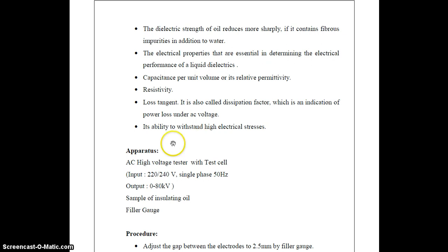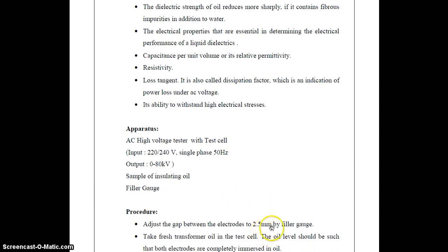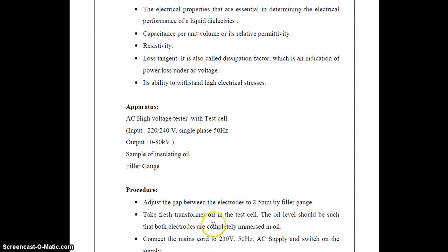Then the apparatus required for dielectric strength of liquid material is an AC high voltage tester with test cell. Input voltage is 220 volt to 240 volt, single phase, 50 hertz. Output is 80 kilovolt. A sample of insulating oil and a filler gauge are needed. Procedure: adjust the gap between the electrodes to 2.5 mm using the filler gauge. Take fresh oil in the test cell. The oil should be such that both electrodes are completely immersed in oil.